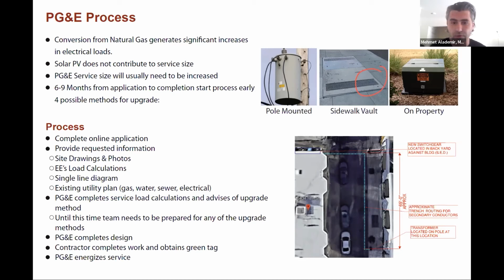There are several ways to do it: they can use the existing transformer, add a pole-mounted transformer, put it in the sidewalk, or put it on the property. For our project, our threshold was 400 amps, and since we're adding 3 more units, 80 units total, we exceeded that number, so PG&E literally asked us to put a transformer in our backyard.